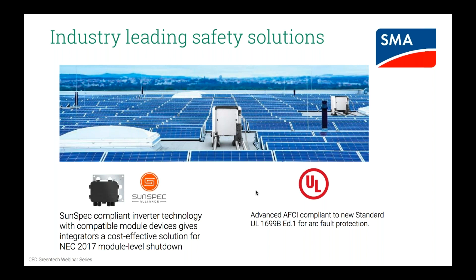I'm going to talk about two key features related to safety that we're providing in the Core 1. The first being our solution for the module level rapid shutdown that's required in NEC 2017. And second is the arc fault protection, or AFCI, that's built into the inverter. So let's start with module level rapid shutdown.